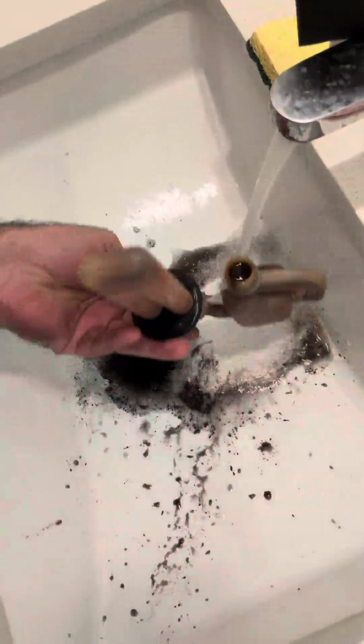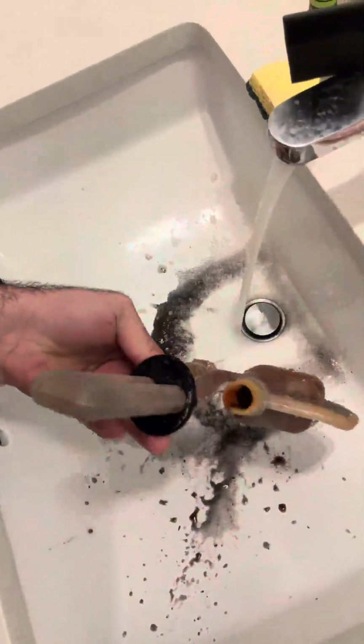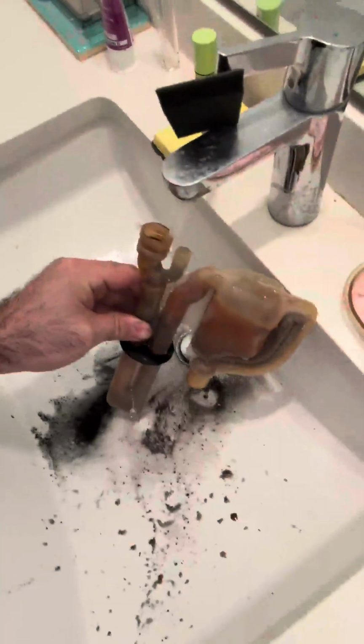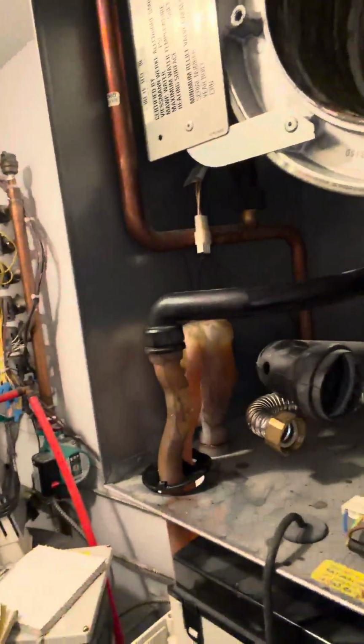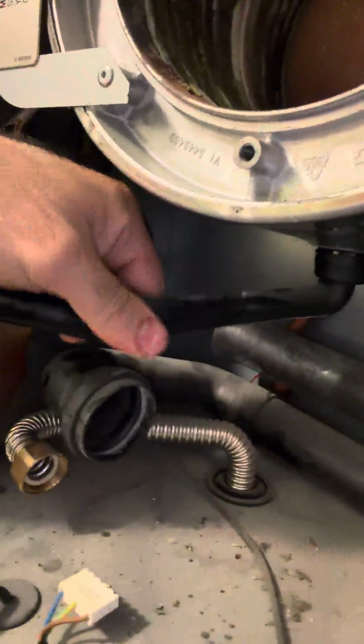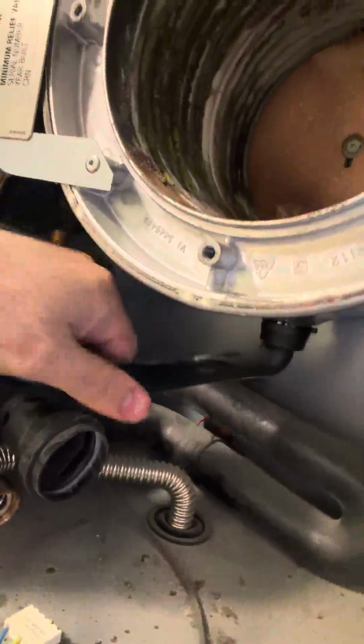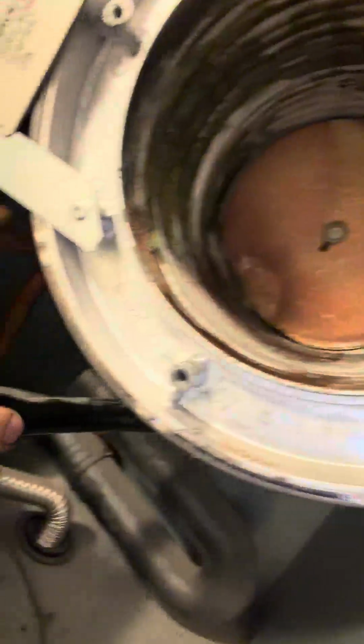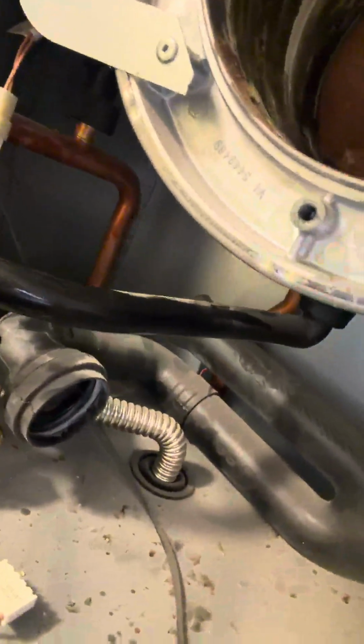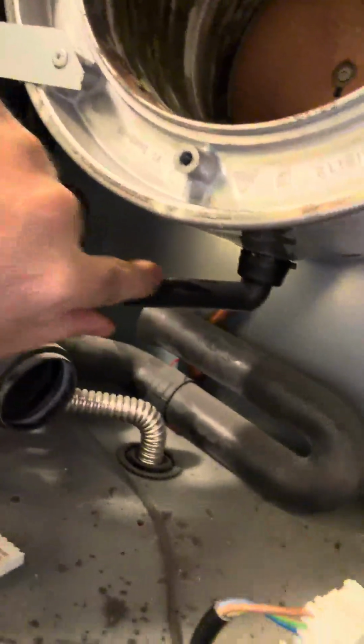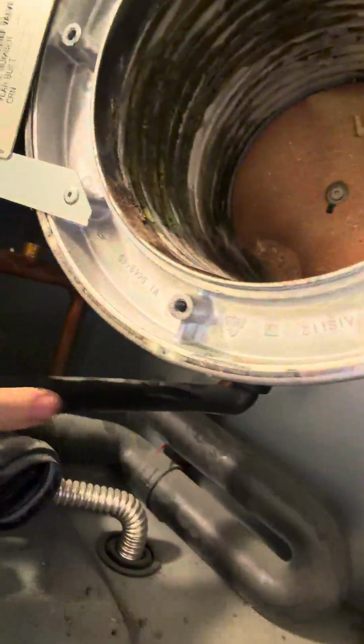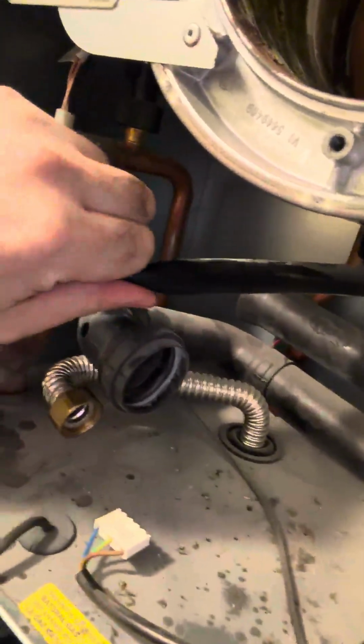You can see how dirty it is, this P-trap. That's gonna be clean now. I'm cleaning it right now. So after cleaning, I put that back. Also, there was a lot of dirt in this hose as well. I put some water in here and drained that dirt into a separate bucket, then put that back on here. That's really important, because if this hose is plugged, the condensate would not go into the P-trap, and that would be a problem. That could be because of the F4 problem as well.